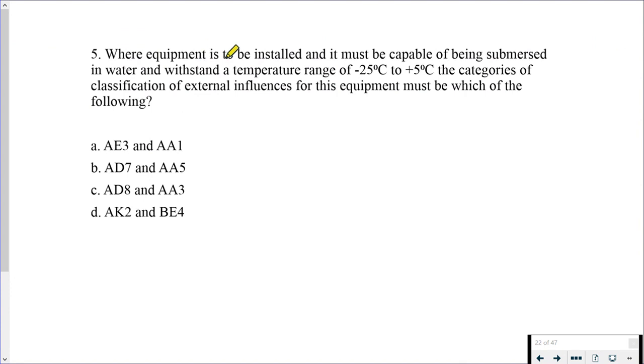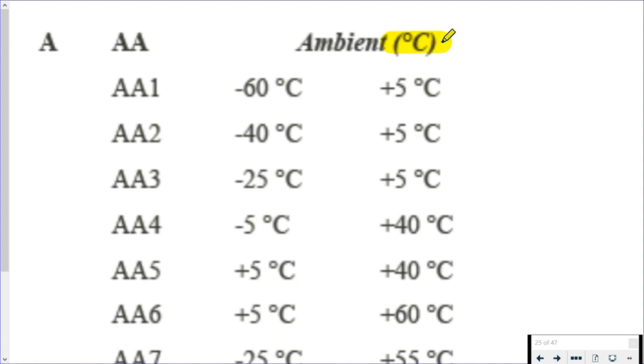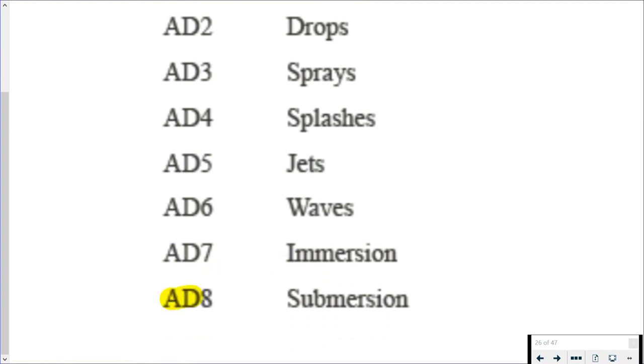Question 5: where equipment has to be installed and it must be capable of being submersed in water and withstand a temperature range of -25 degrees to +5 degrees C, the categories of classification of external influence for this equipment must be which of the following? We've got a list of external influence codes. We're looking for external influences. We find that in Appendix 5. When we're in Appendix 5, we're looking for water and temperature ranges. There's the temperature range and the fact that for water, the equipment is submersed. So Appendix 5, we've got this big concise list. First thing on the concise list is that ambient temperature AA. So AA3 has that -25 to +5 degrees C. And if we look further down to water and we scroll down through water, you'll see that AD8 has submersion.